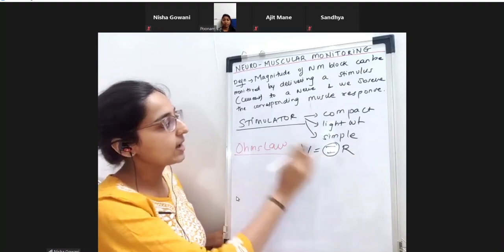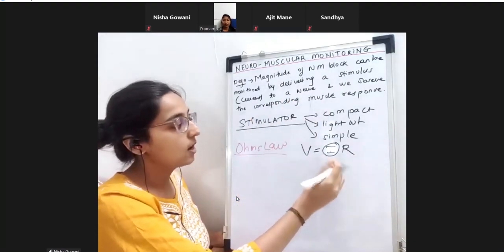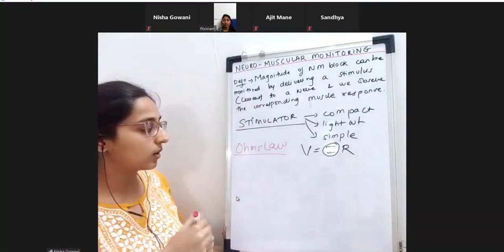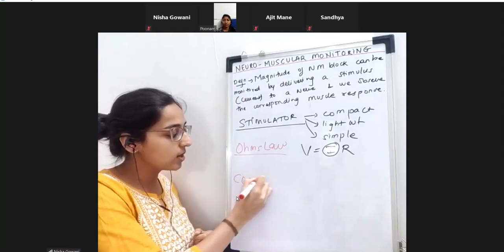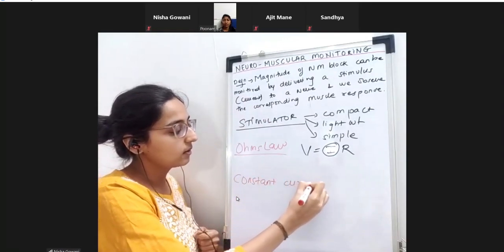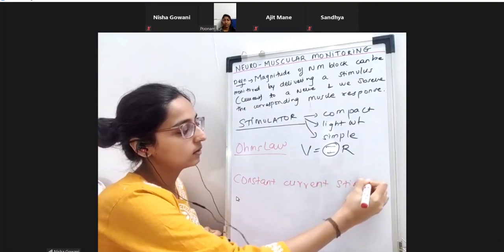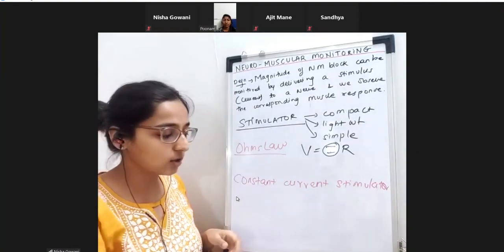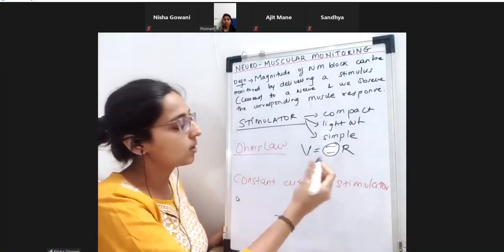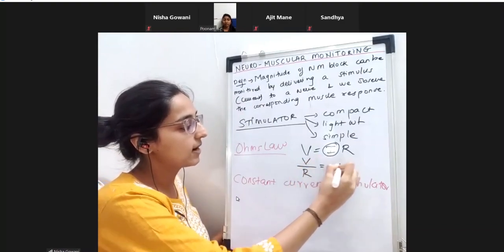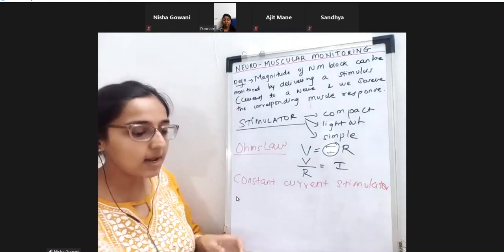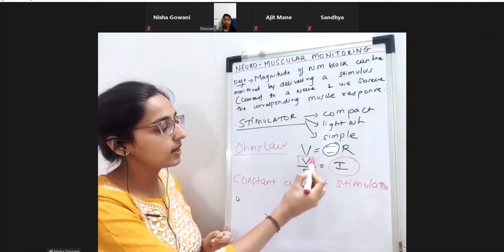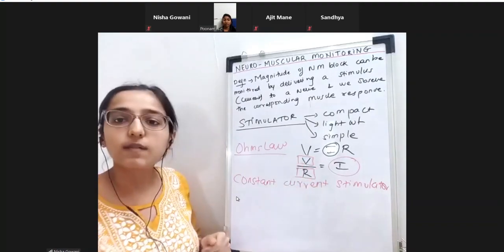We are delivering a particular current I. This stimulator has the property that it will deliver a constant current - it is a constant current stimulator used in the OT. If I is constant, then voltage and resistance will be variable.